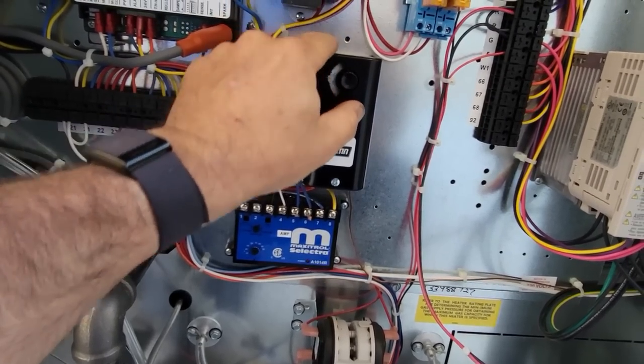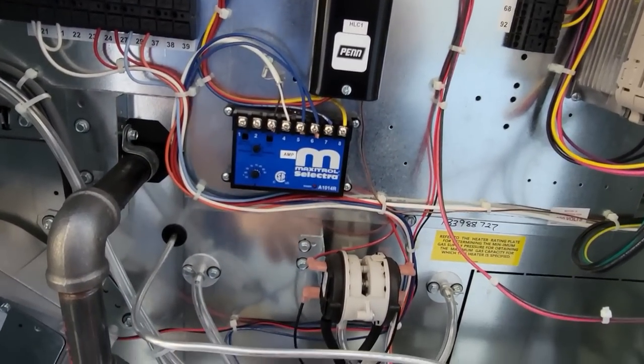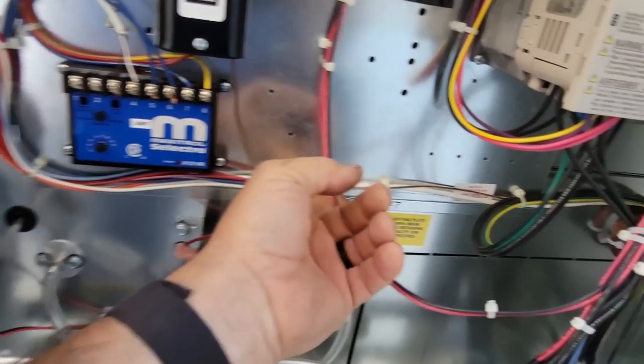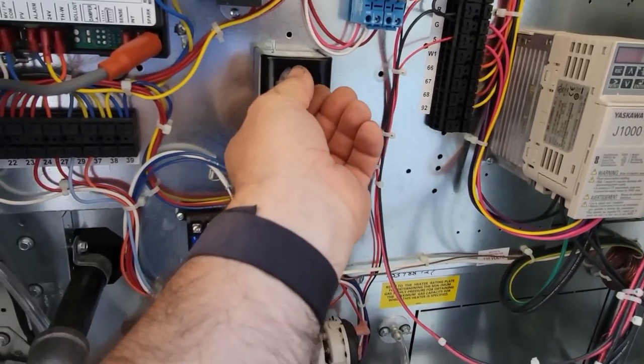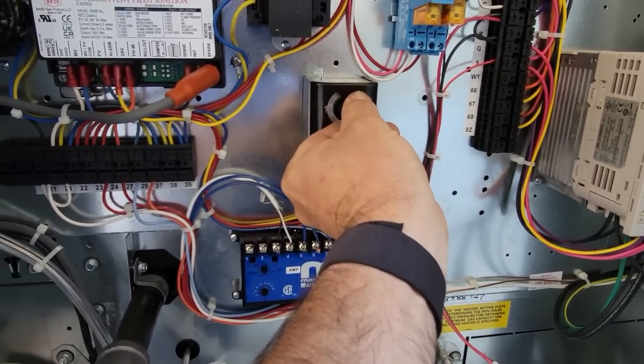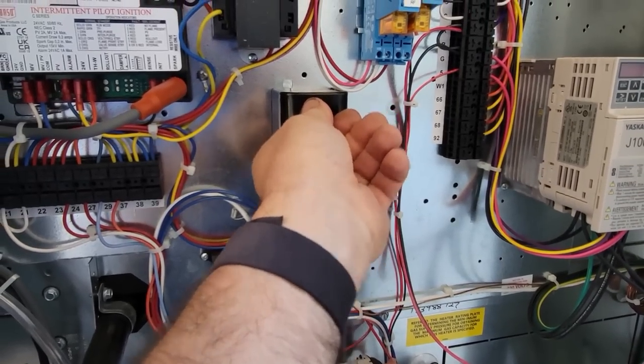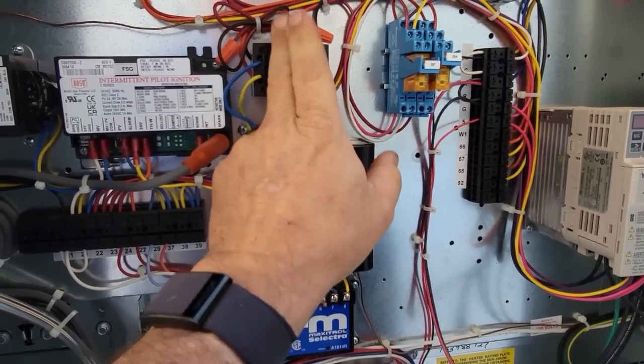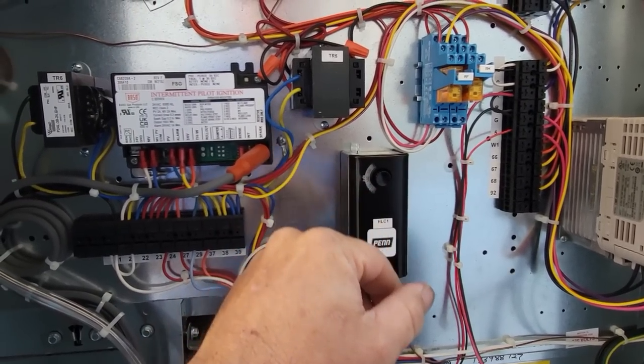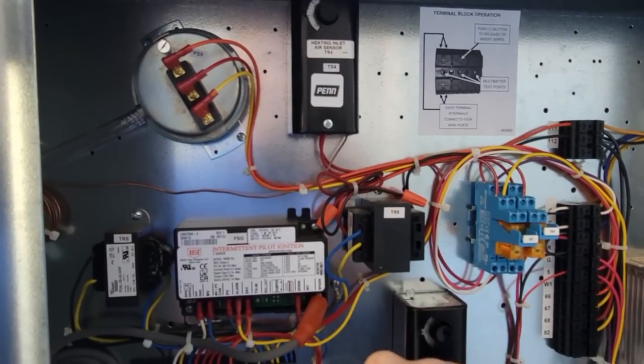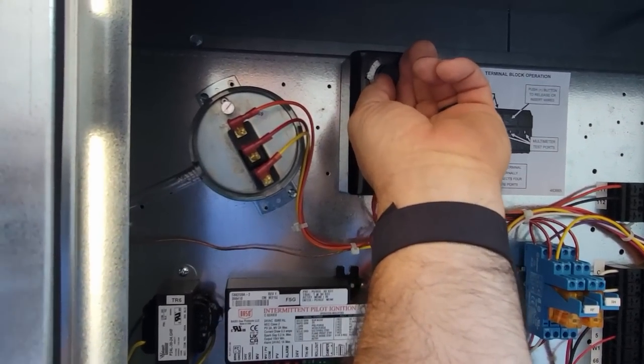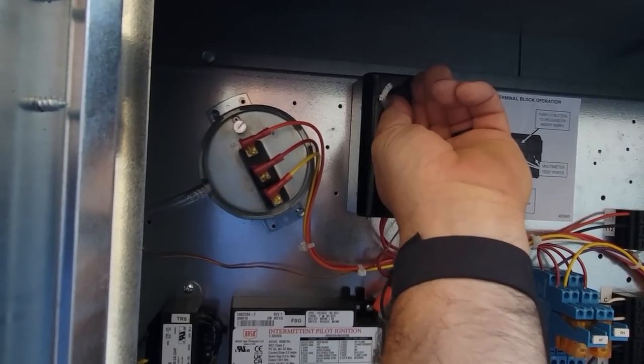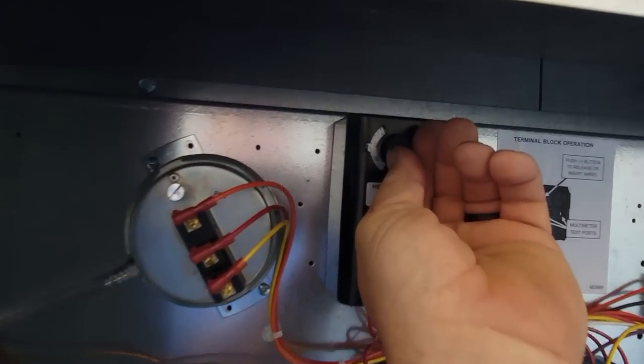Guess that should be the limit, so that if it fails, it shuts down the fan. I'll have to check, make sure. We got two transformers here. We had some wackiness going on with the transformers last time. Heating inlet sensor, so it has to be at least that temperature for it to run. Usually I think we set her about 55 degrees.